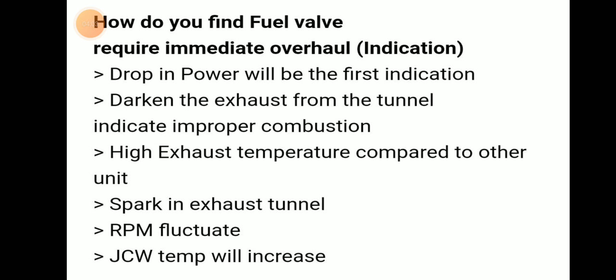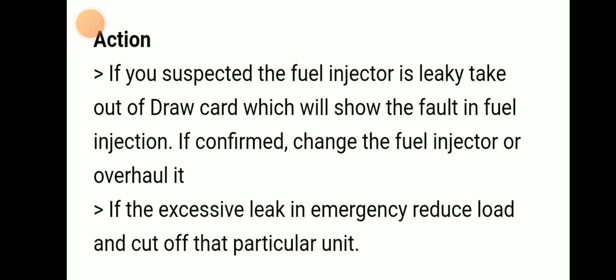If you suspect a particular fuel injector is leaky, take the draw card. If it shows there is a fault in the fuel injection, then it is confirmed. Then change the fuel injector or overhaul it. If the leak is excessive, then in an emergency, reduce the load and cut off that particular unit.